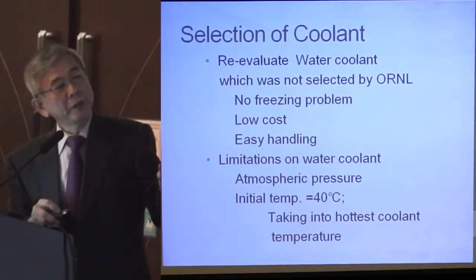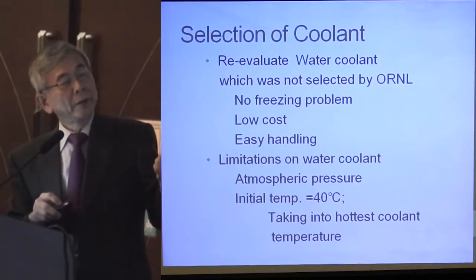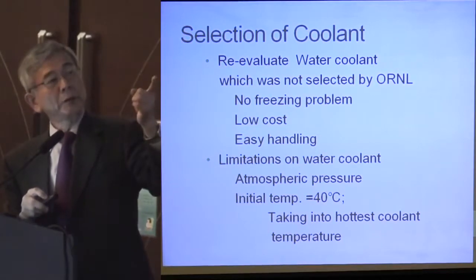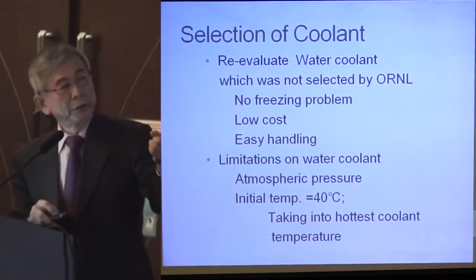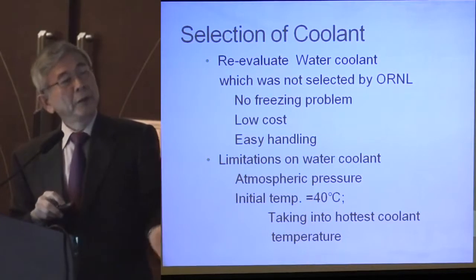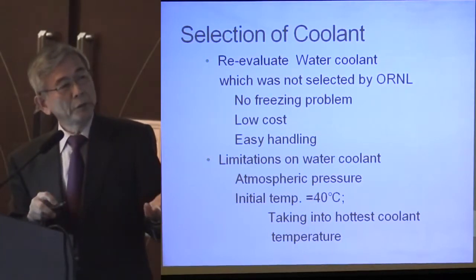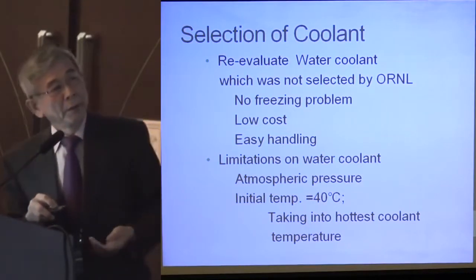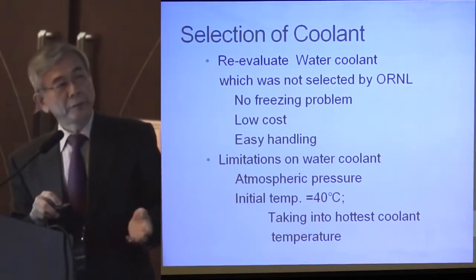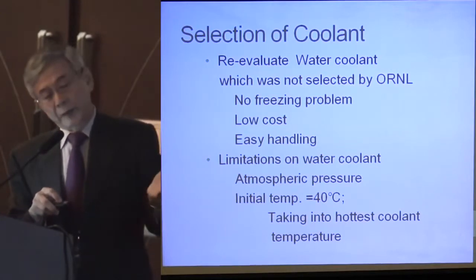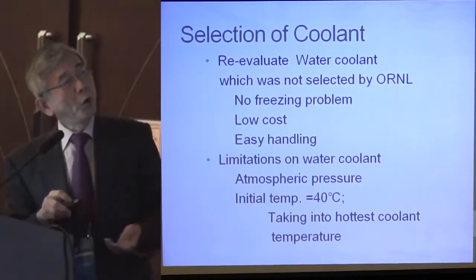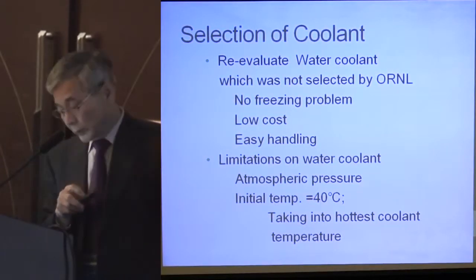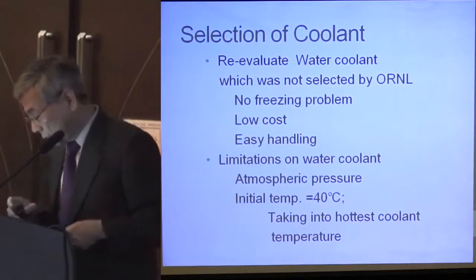We assume the higher temperature because the water may reach boiling point when the initial temperature is higher. So we take into account the hottest coolant temperature. That means during summer, maybe 40 degrees Celsius can be expected. So we set the conditions like this.